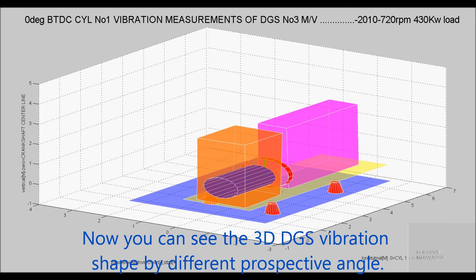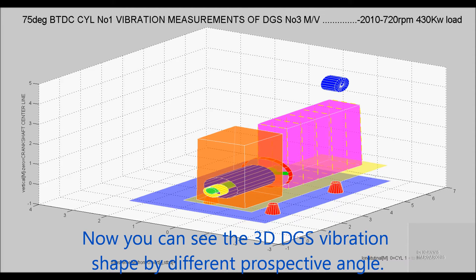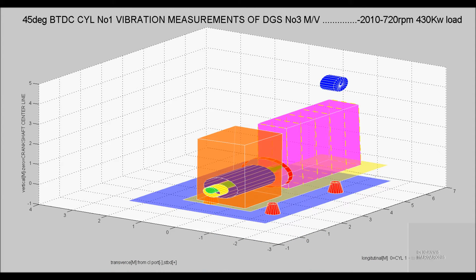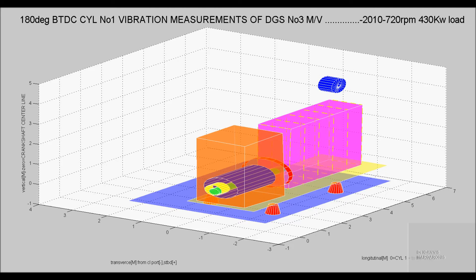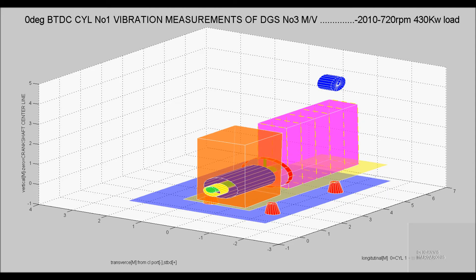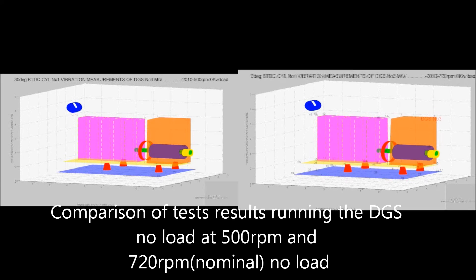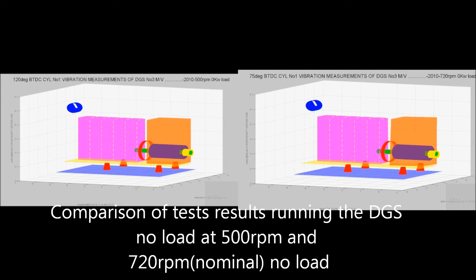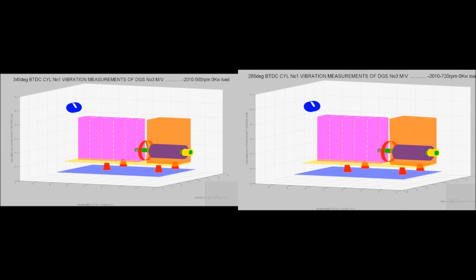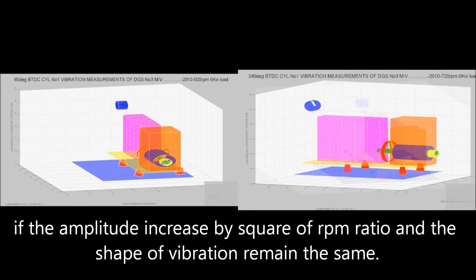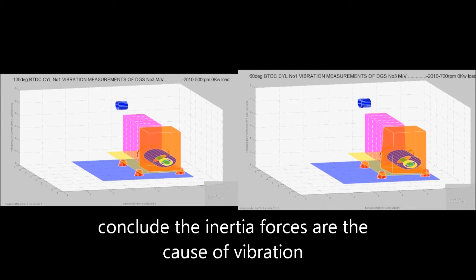You can now see the 3D DGS vibration shape from different perspective angles. Comparing test results running the DGS at no load at 500 RPM and 720 RPM nominal no load: if the amplitude increases by the square of the RPM ratio and the shape of vibration remains the same, we conclude that inertia forces are the cause of the vibration.